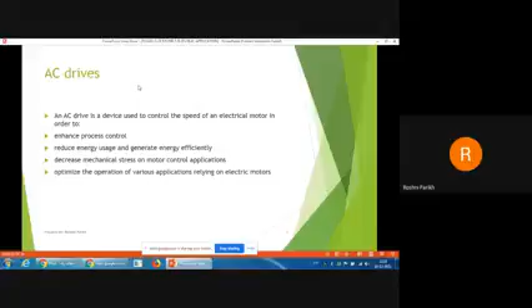What is the block diagram of an AC drive? See here, a three-phase AC input is there. Here a converter is there. Converter means a rectifier, which converts three-phase AC into a controlled, that means variable, DC output voltage, because the power converter is using SCRs to get the control voltage at the output side, not a fixed DC but a variable DC supply. Then it is given to a DC bus, and then to the inverter, because here we are going to drive the AC motor, so the input should be AC. So here a rectifier, then DC bus, and then inverter. The inverter again converts the DC into AC.